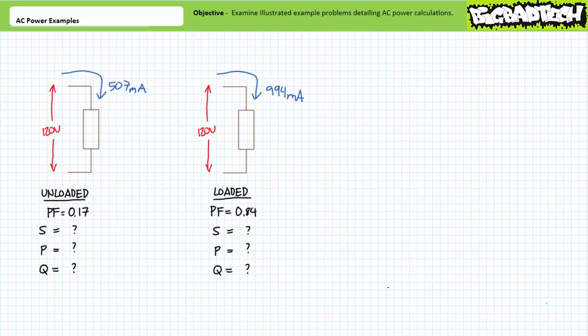This is evident by the poor power factor of 0.17. Really, the only thing the 507 milliamperes of current drawn from the power supply in the unloaded condition is doing is establishing a magnetic field and maybe accounting for a tiny amount of real power lost due to heat or friction. In the loaded condition, however, a substantial amount of work is being done, evident by the much larger power factor of 0.84. However, the motor still requires a magnetic field to operate. Thus, we'd still expect a portion of power to be directed towards a reactive interchange.